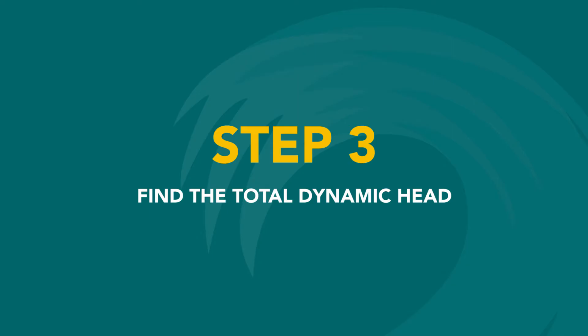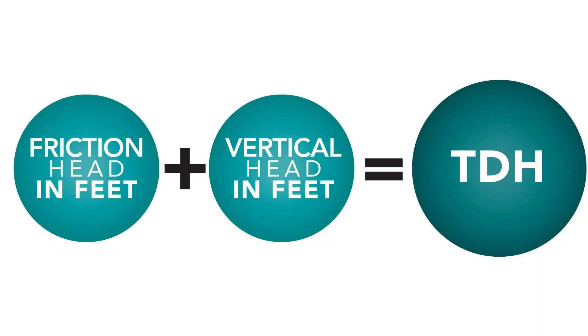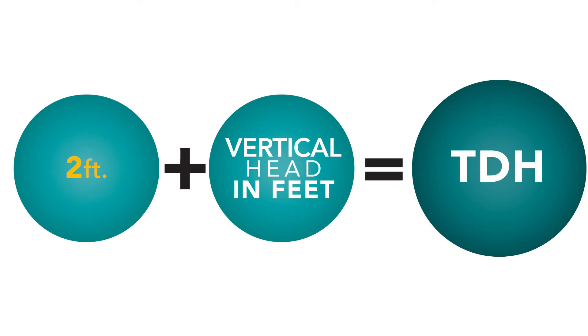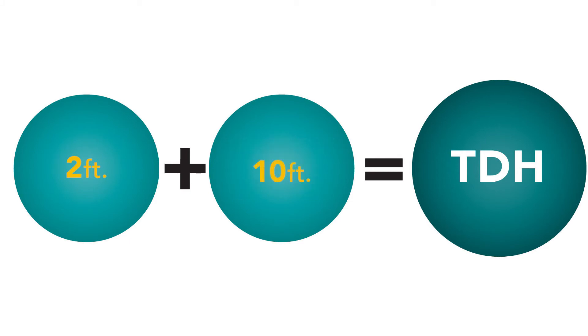Now it's finally time to calculate the TDH. We'll simply add the friction head of 2 feet to the vertical head of 10 feet, to find that the TDH is 12 feet.